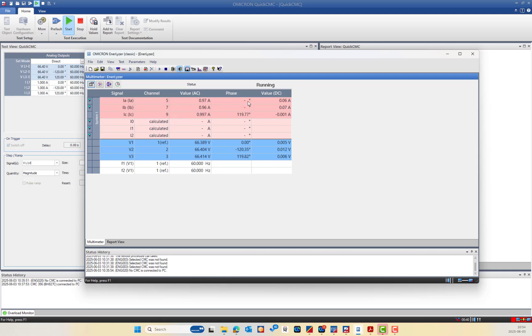Why can we only see the IC phase angle? IB and IA cannot be measured right now because you need to inject more than 2% of the maximum expected current. For IA and IB using a 1 mV/A clamp ratio with a 100 mV range, the current range equals 100A. To measure the phase angle, I need to inject more than 2% of 100A, which means more than 2A.